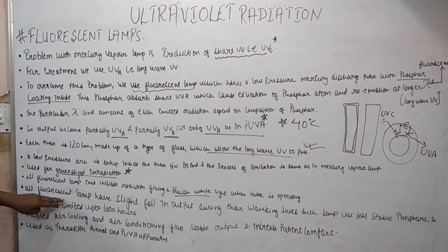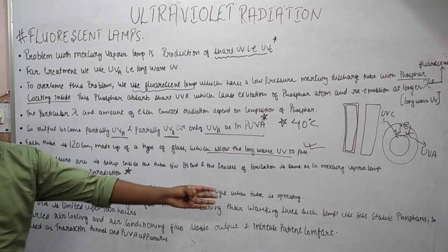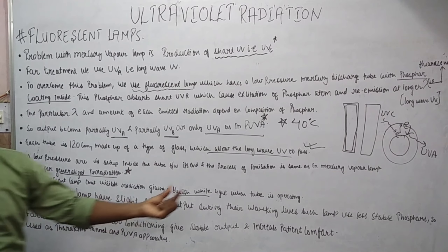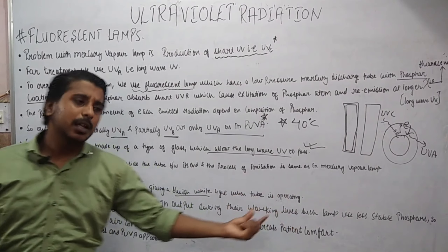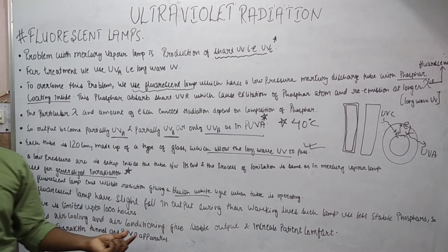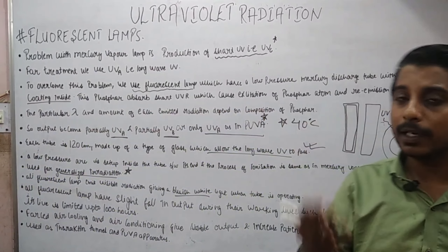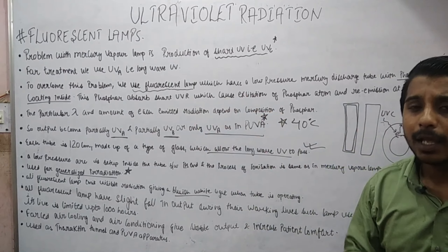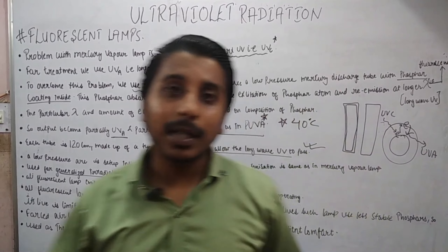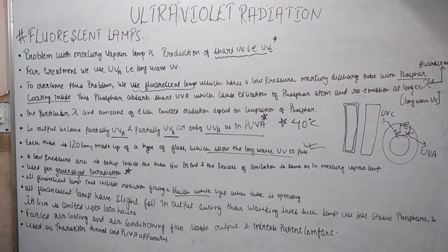All fluorescent lamps have a slight fall in output during their working life. The reason is that some fluorescent tubes use less stable phosphor, so they can only be used up to 1000 hours. Some fluorescent tubes have a sharp drop in output because they are made up of unstable or less stable phosphor, and after 1000 hours we need to replace them.